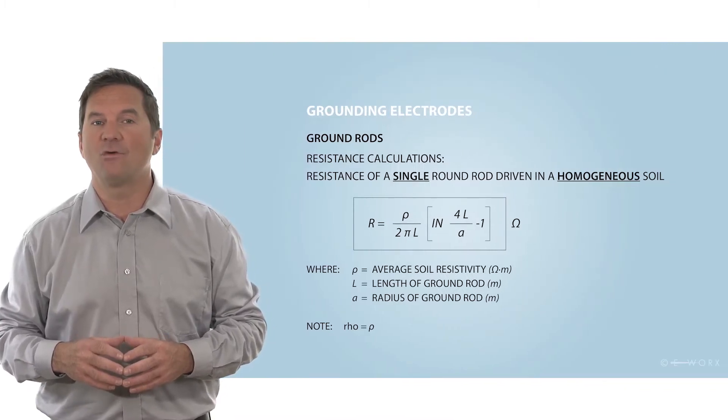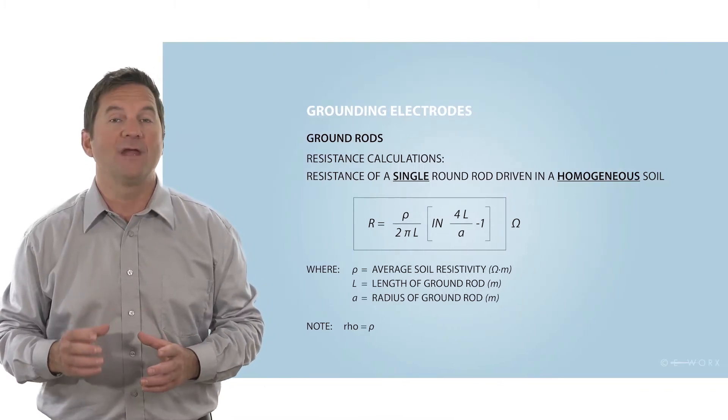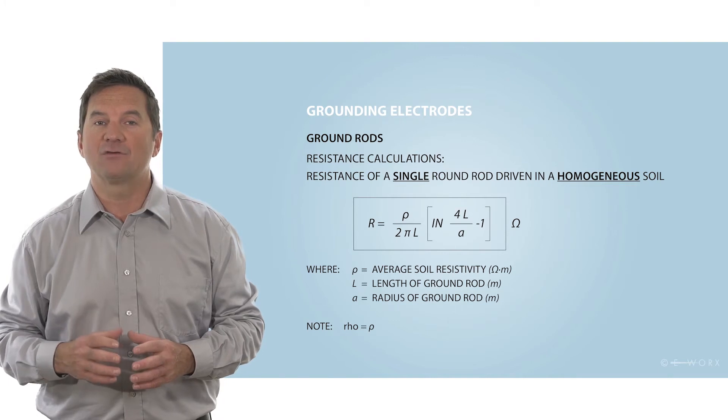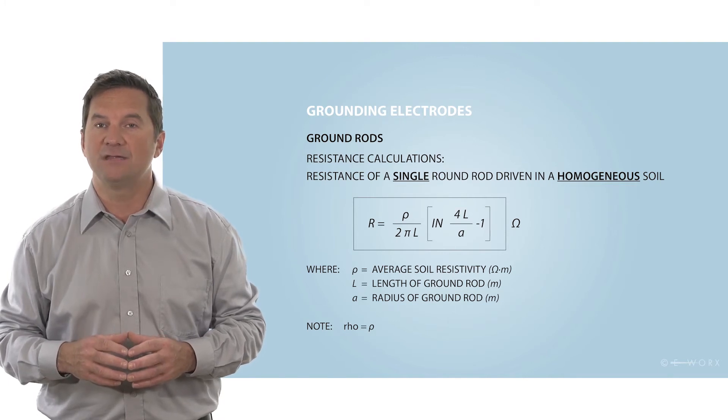The resistance of a single rod of length L and radius A driven into the ground with soil resistivity RHO is given by this equation. Now we'll perform the same analysis for touch voltage.